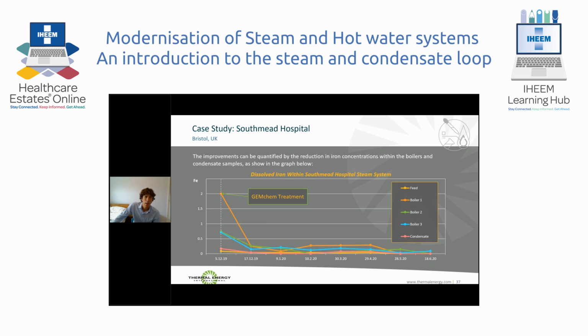Here we can see the iron level in parts per million. You can see a rapid drop following the GemChem treatment being started across the feed water, all 3 boilers, and the condensate return. The hospital are very, very happy with this and have continued the treatment program.